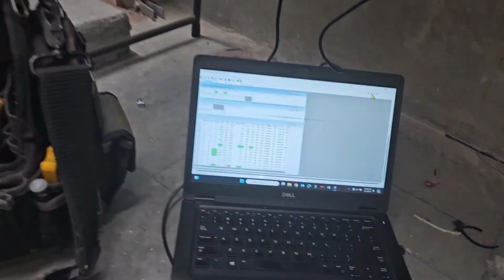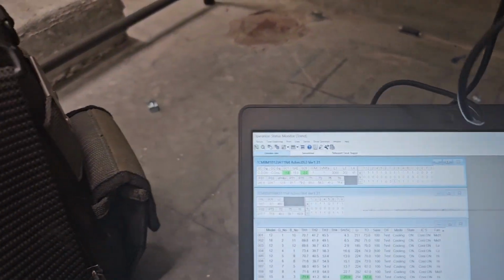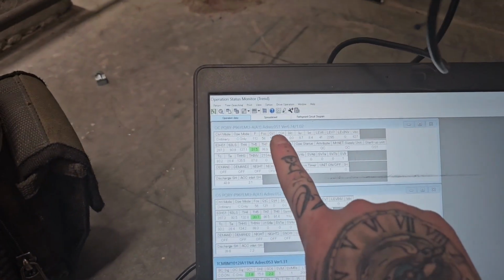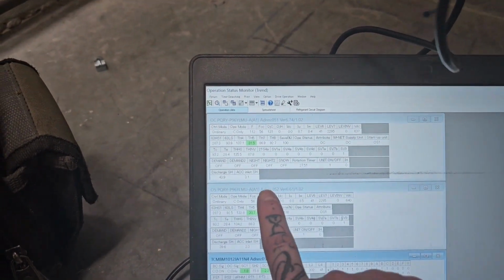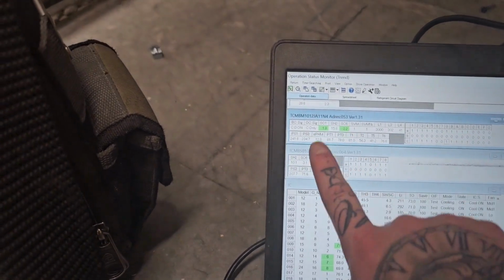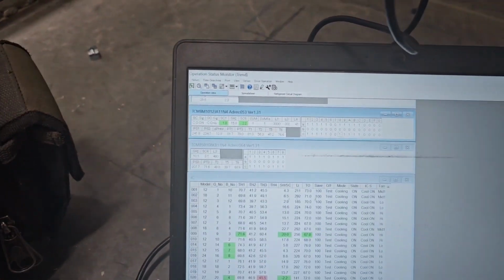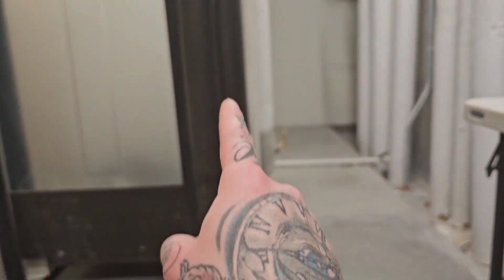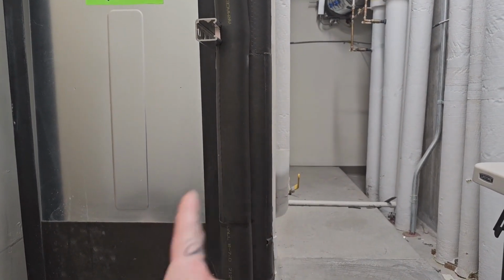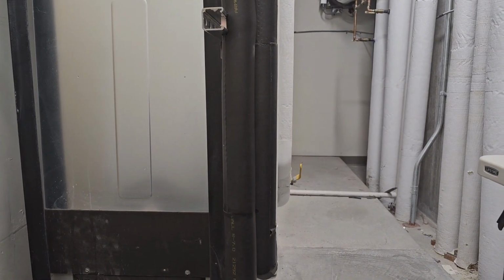Then I can pull it in, and while I'm here, I can look and say, okay, my outdoor unit is address 51, 52, we've got a 53 BC, and then we've got a 64 sub BC. I can pull those panels off and say, okay, this one's 51, 52, so these are the units we're looking for, right?